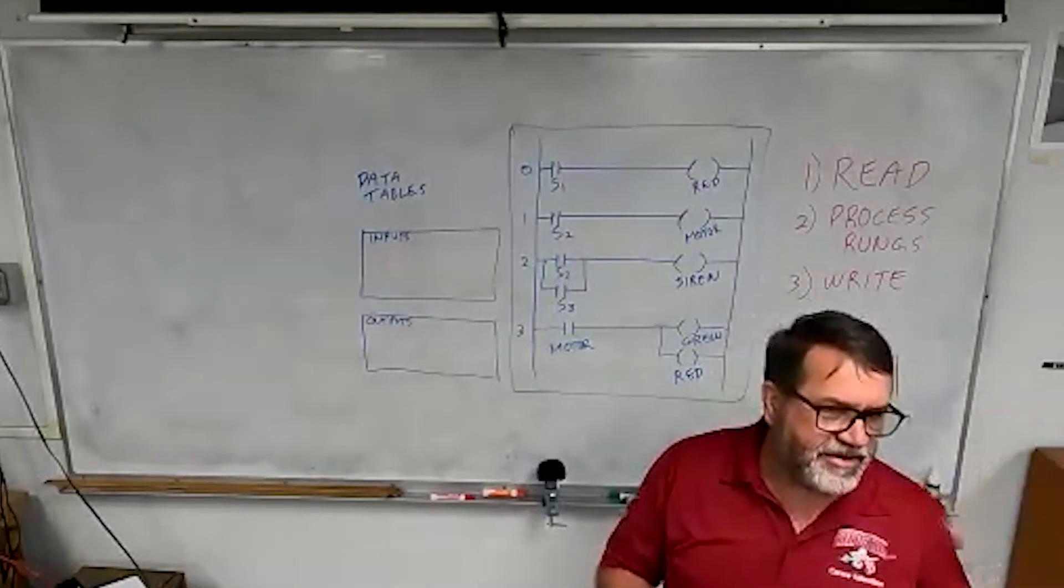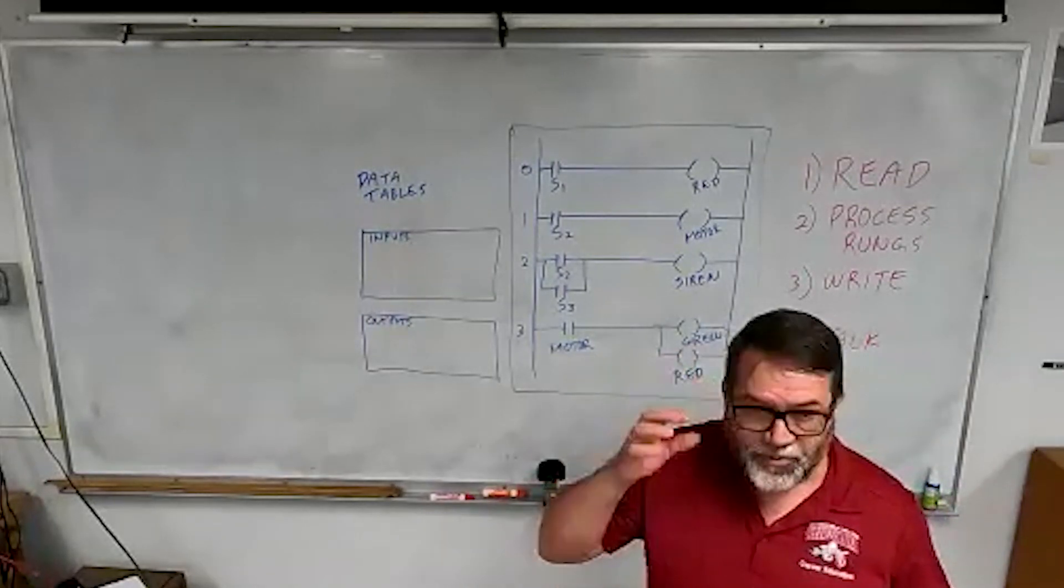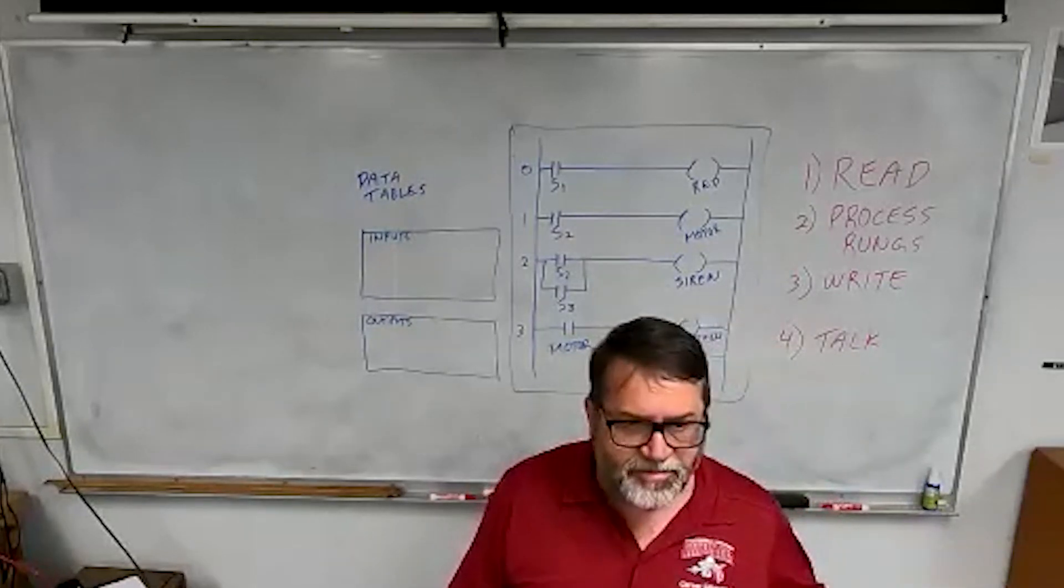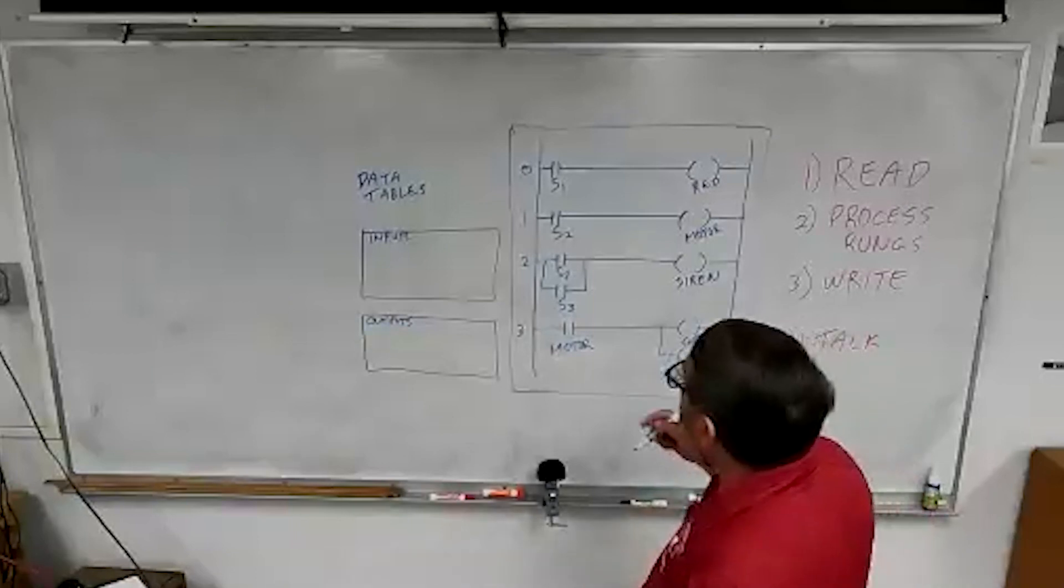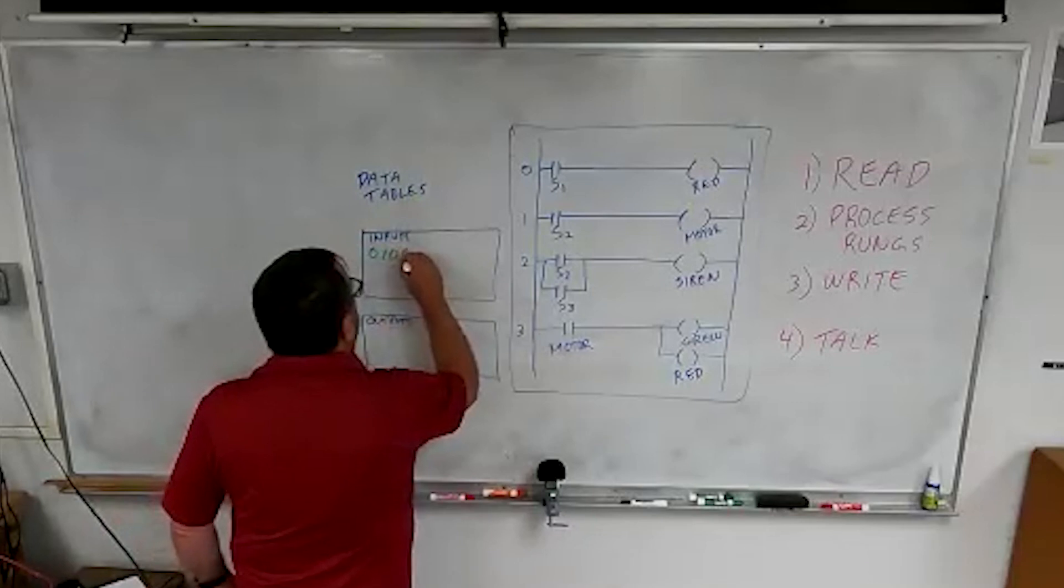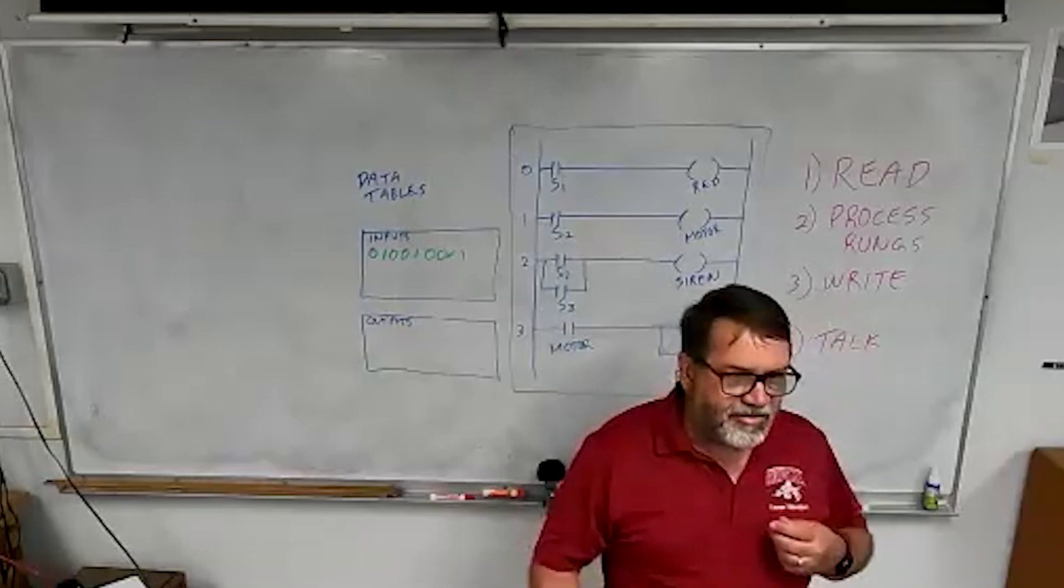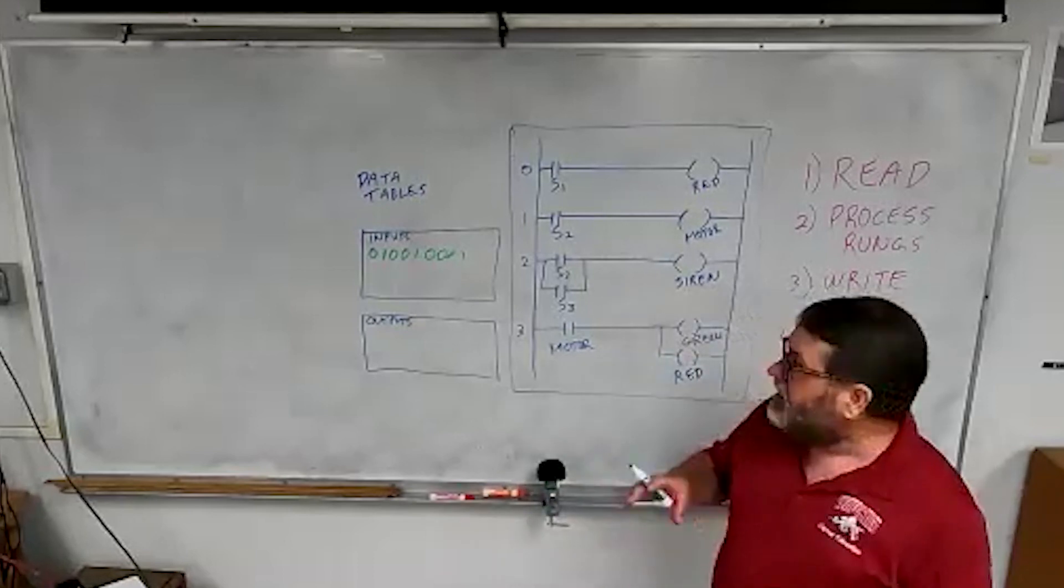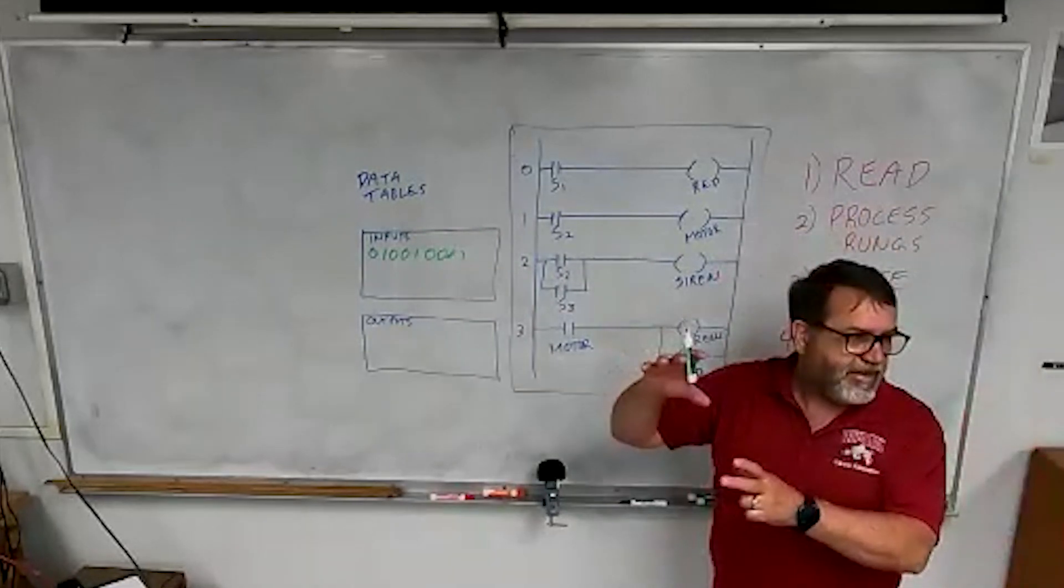The first step is when they read. So they go out, and they look at all the inputs, and they read what inputs are hot. So on your trainer panel, you've got buttons that you can push, and that will send a hot signal into the PLC. So when they read, they're going to look at all the inputs, and they're going to update the tables, and they're going to just make a recording of what's hot and what's cold. And that's all they do in that step. Now they don't go back and read again until they come back around to step one. They read it one time, and that's it.